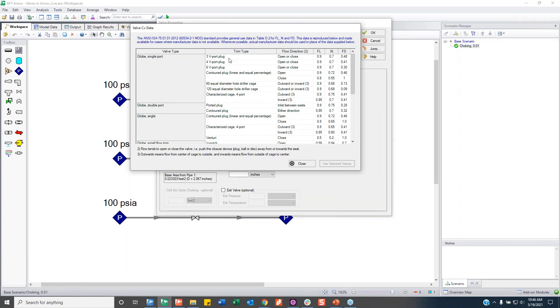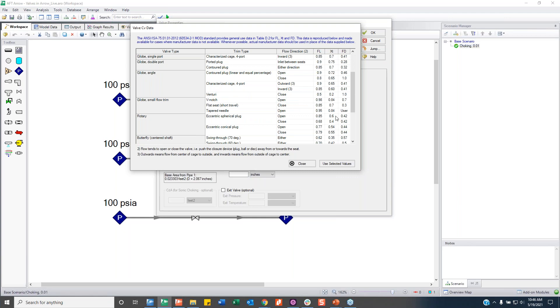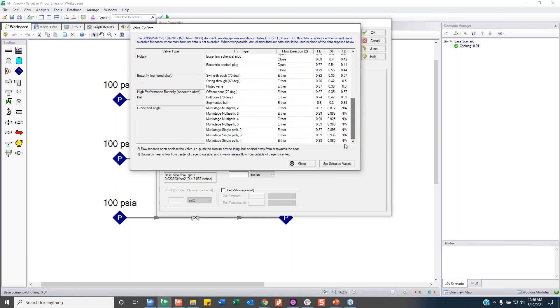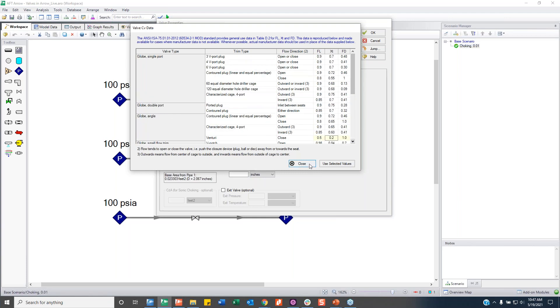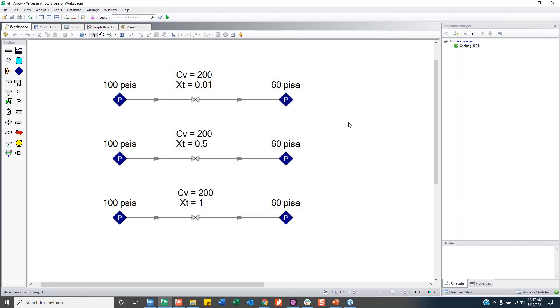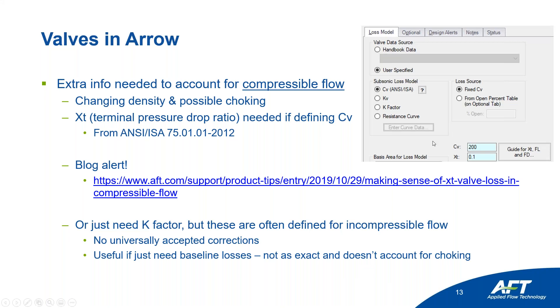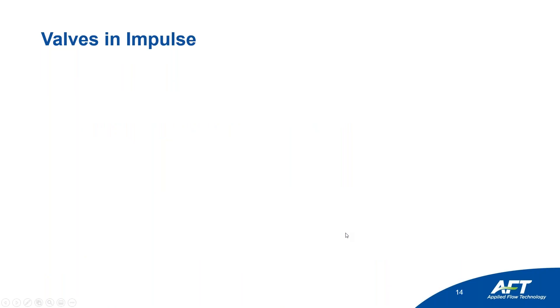Use the xt guide table — the lowest realistic value from the literature is about 0.2, and the highest around 0.7. You'll never get to 0.01 in practice, so don't worry about extreme sensitivity. Just test your system with a reasonable range, because xt might not be a significant factor — it is required for the math and the ANSI standard, but in many cases the sensitivity is low.